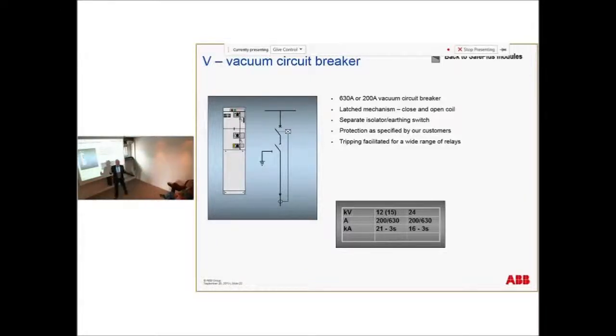In all switchgear that we deliver, let's say the hierarchy of the interlocking: the vacuum circuit breaker is interlocked with the disconnector. The disconnector is interlocked with the earth switch. This is always in our switchgear. In addition, you can ask us to also interlock the cable covers with the earth switch, and then you need to earth in order to open this cover. But you need to specify to Valur or to Asgeir that you would like this cover to be interlocked. We can make this cover interlocked, but it will be mechanically interlocked.